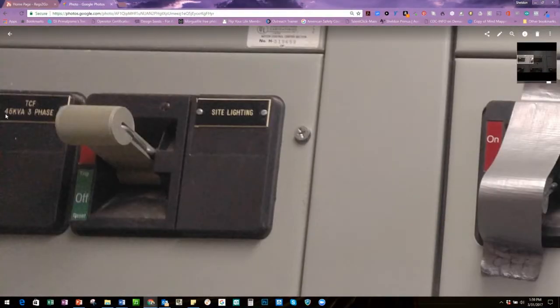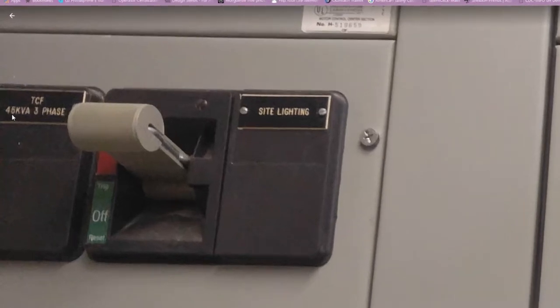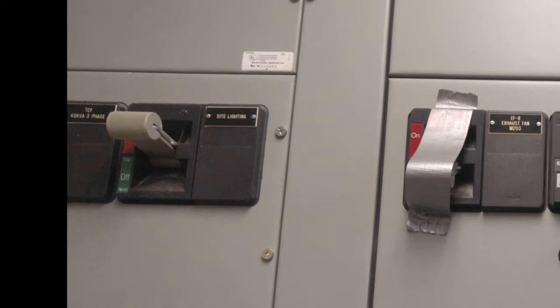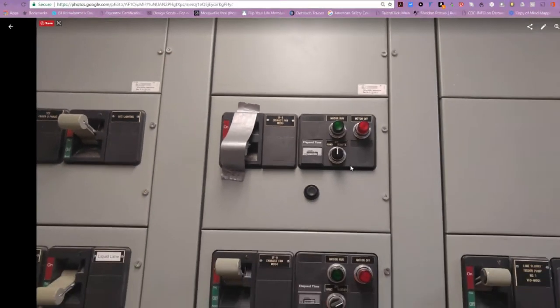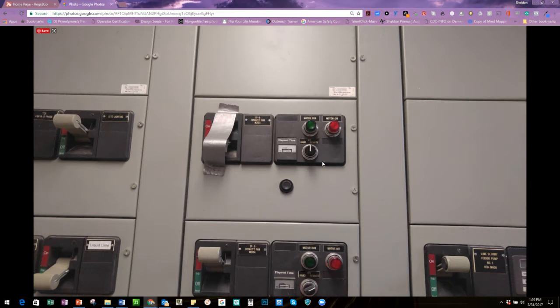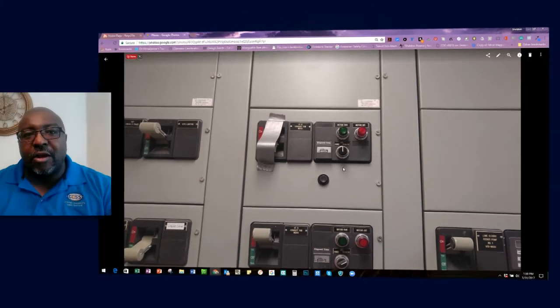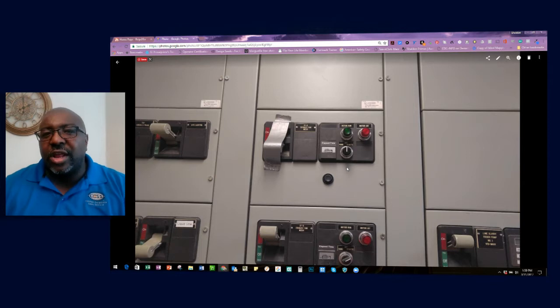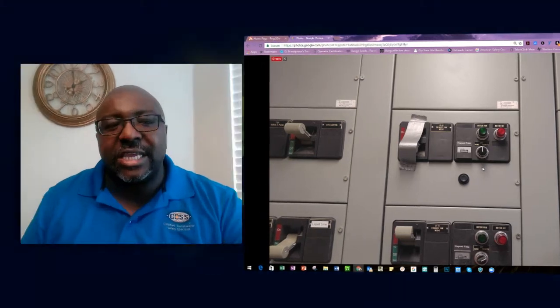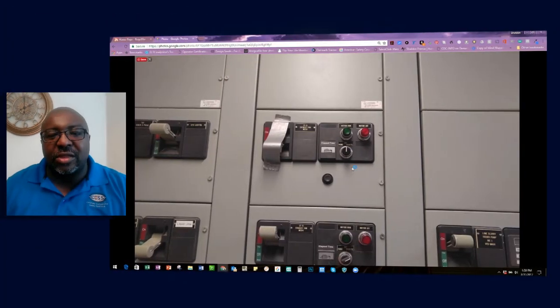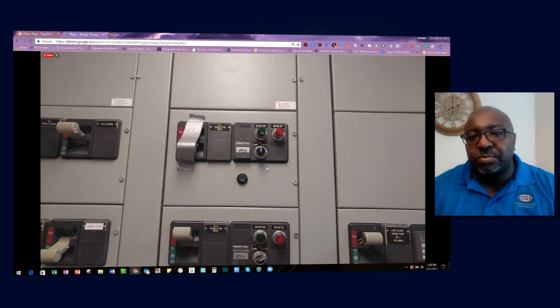In the very corner, it tells me I've got a 45 kVA three-phase, so it's very high voltage. However, there is no other wording here to let me know what is my arc flash rating, my arc flash hazards, what type of PPE should I be wearing, or my approach distances. So there's no labeling alerting me, as the novice, to what I can do if this panel is actually open with exposed electrical, or what my potential hazards are.